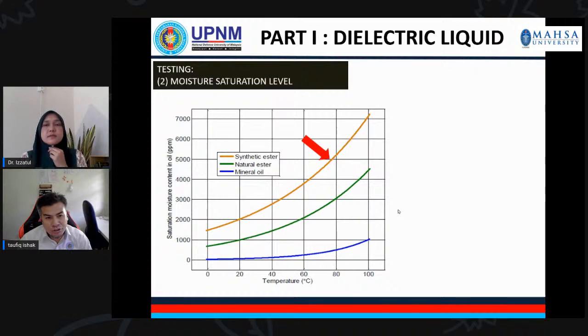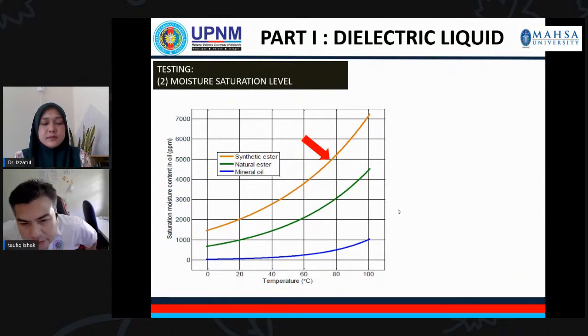Then we look at the second one, which is the moisture saturation level inside the oil. In the insulation area, it is well known that moisture in oil has a detrimental effect and can make the transformer performance worse if you have more moisture inside the transformer. This moisture will deteriorate your transformer insulation material, which is either your oil or paper insulation. And when it deteriorates your insulation material, of course, it will deteriorate the electrical and also mechanical strength of that particular insulation.